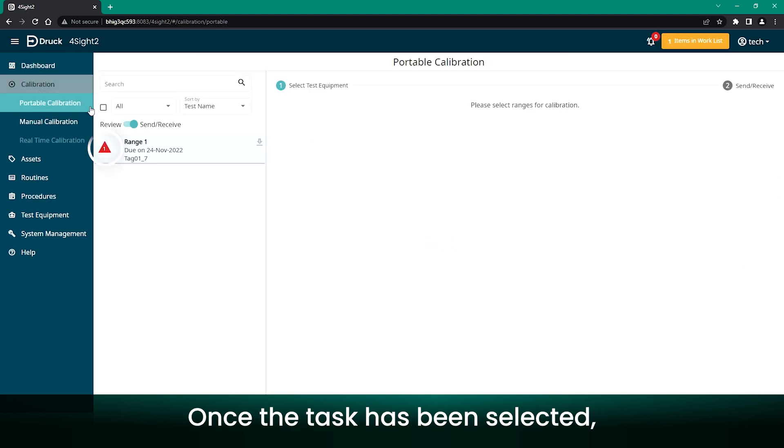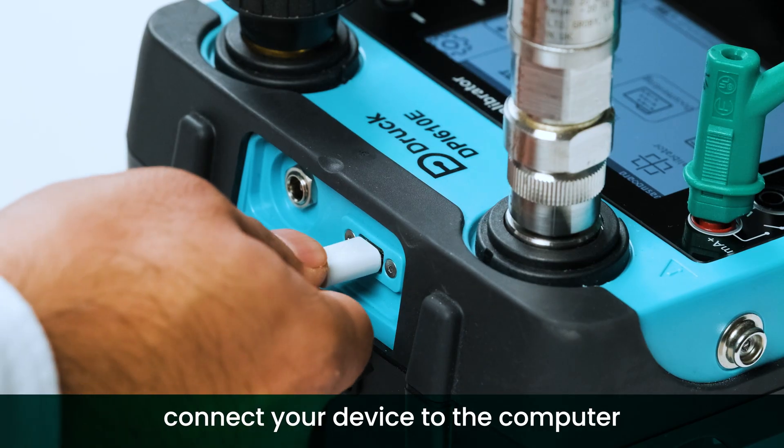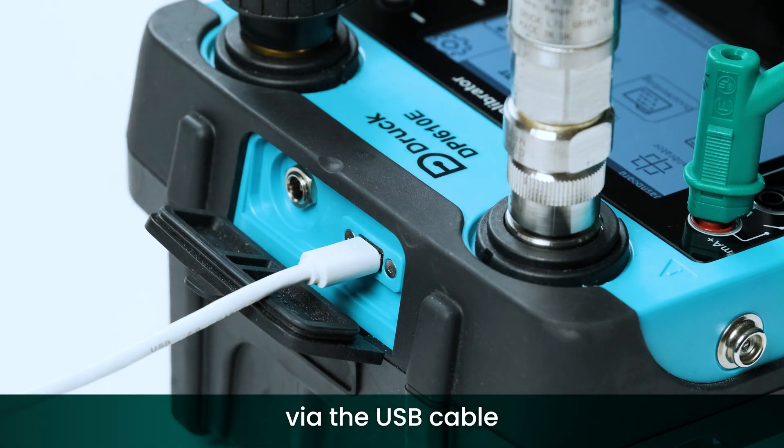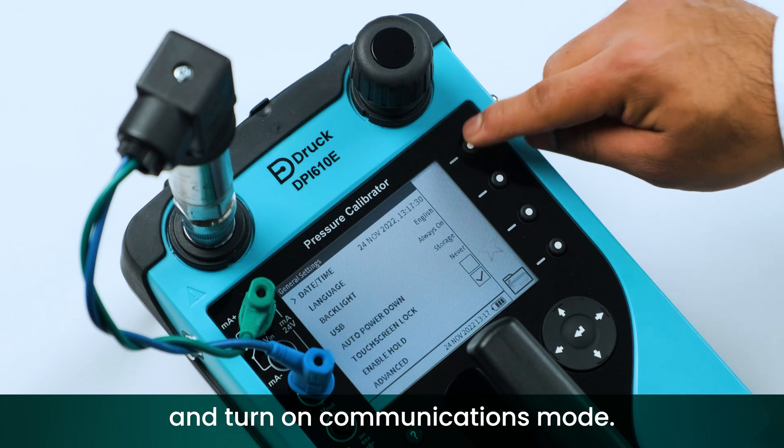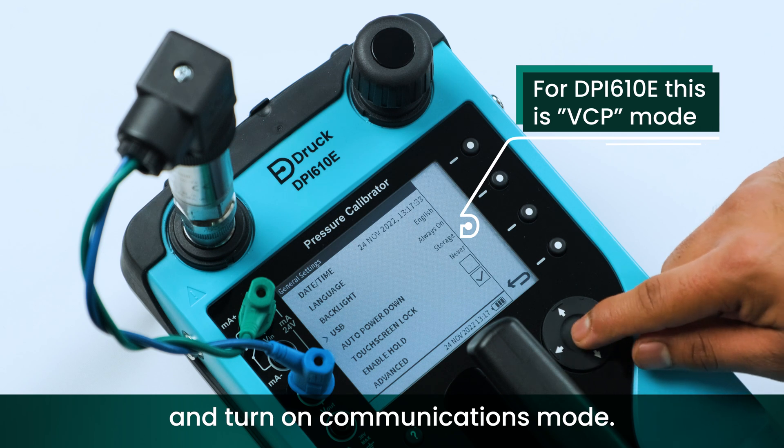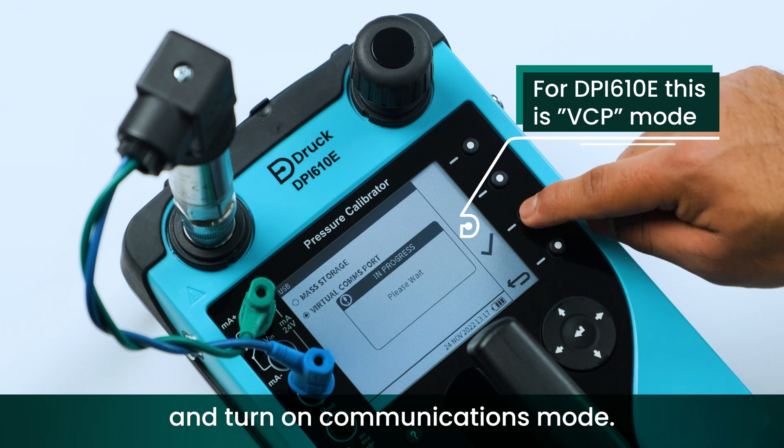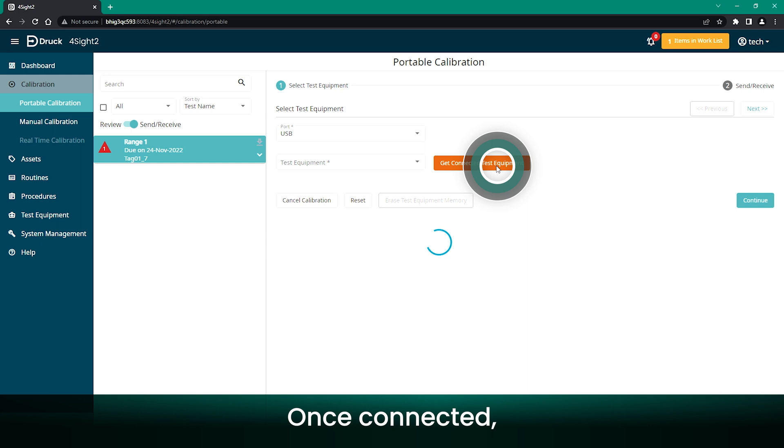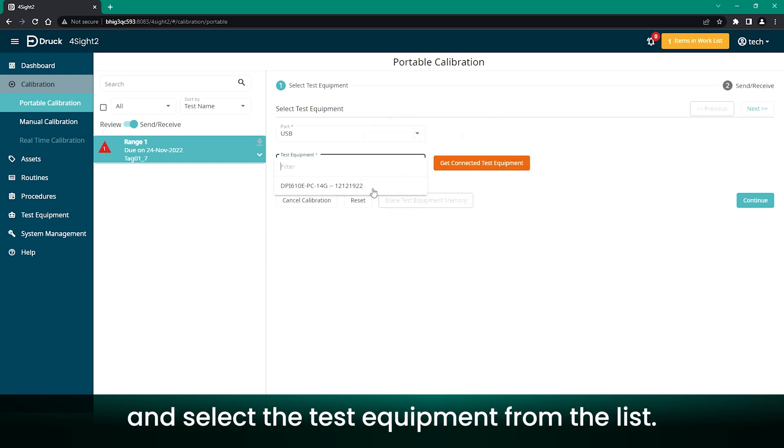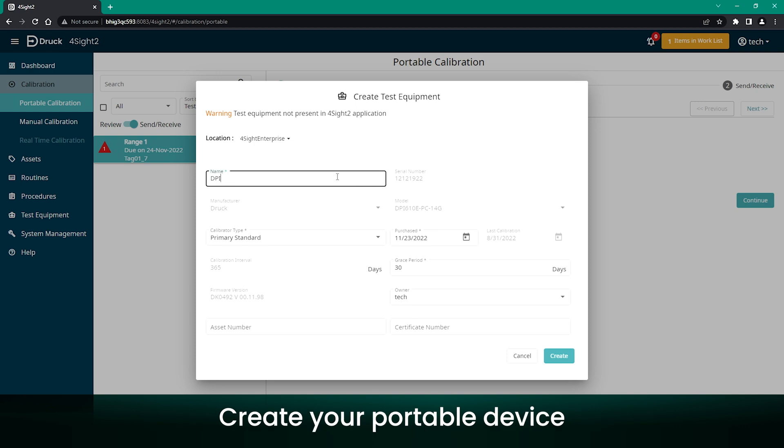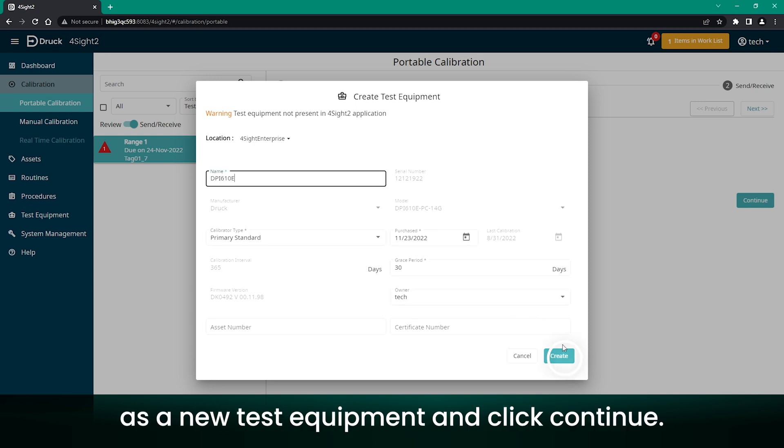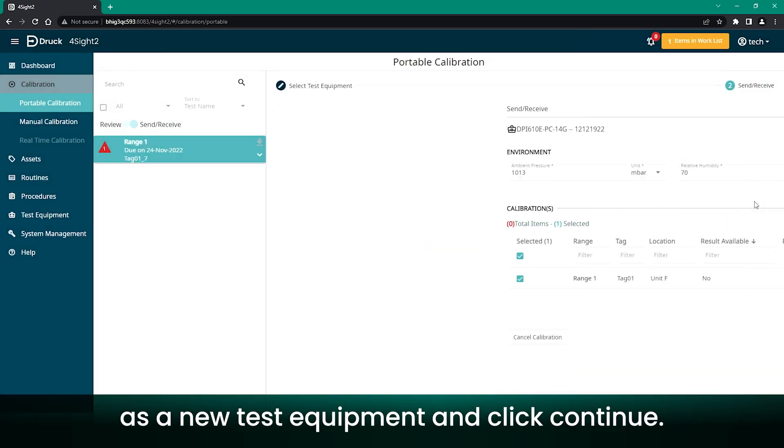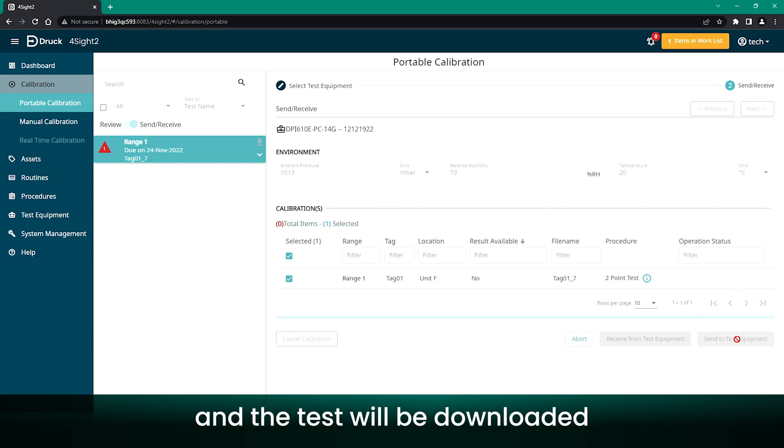Once the task has been selected, connect your device to the computer via the USB cable and turn on Communications mode. Once connected, click Get Connected Test Equipment and select the test equipment from the list. Create your portable device as a new test equipment and click Continue. Click Send to Test Equipment and the test will be downloaded to the Calibrator.